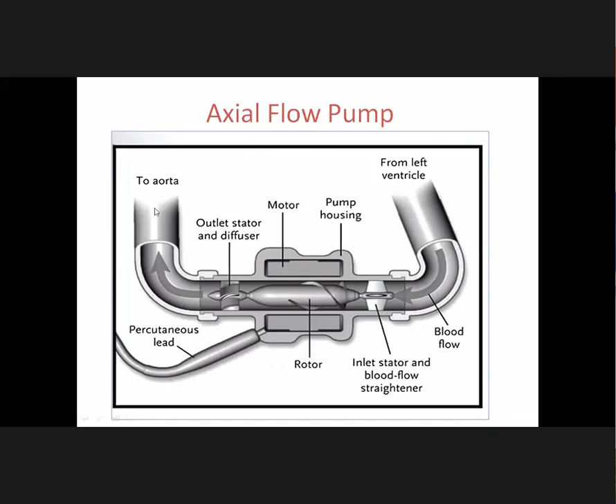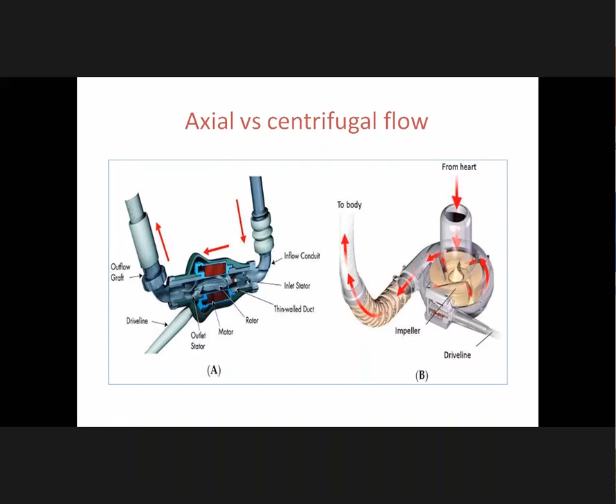This is a comparison. This is how an axial flow machine works, where the blood comes through the inflow conduit. A rotor will be continuously rotating like a turbine, in an axial fashion, which lets out the blood in an axial fashion. Whereas here, the blood goes through the centrifugal turbine, which helps in driving out the blood. I'll tell you the advantages of centrifugal flow compared to axial flow, because the majority of recent LVADs are based on centrifugal flow patterns.